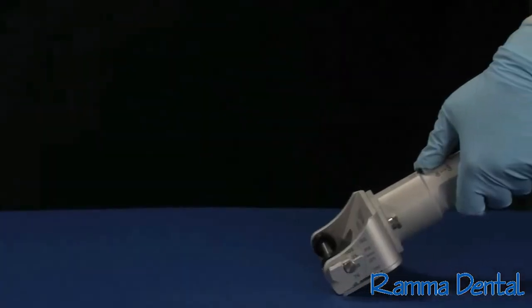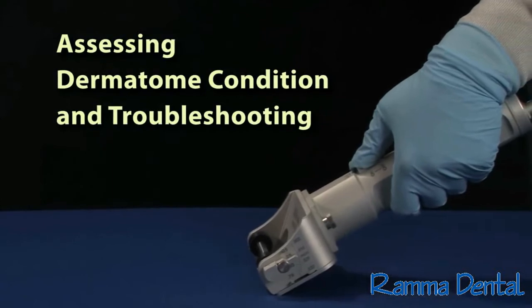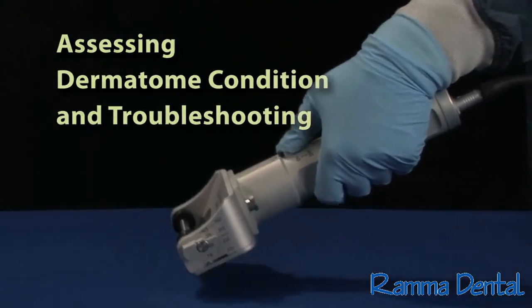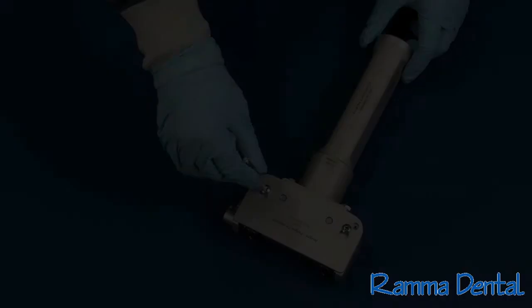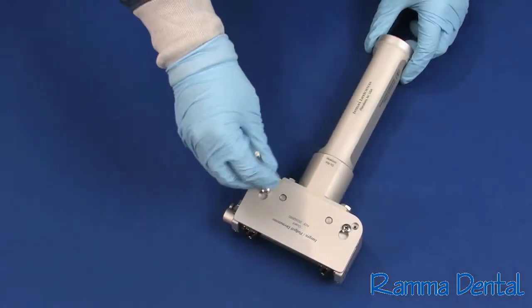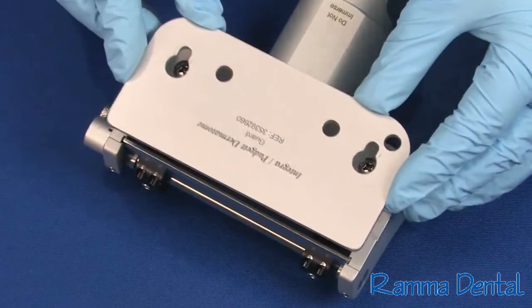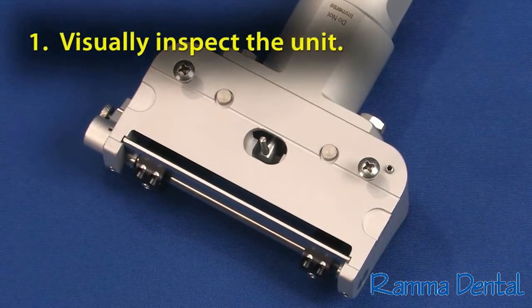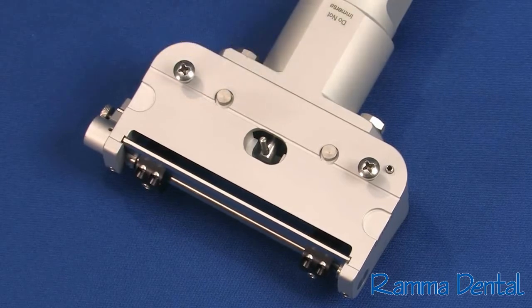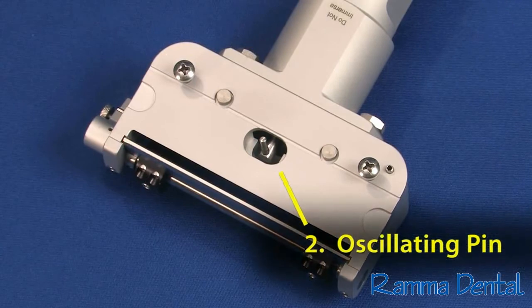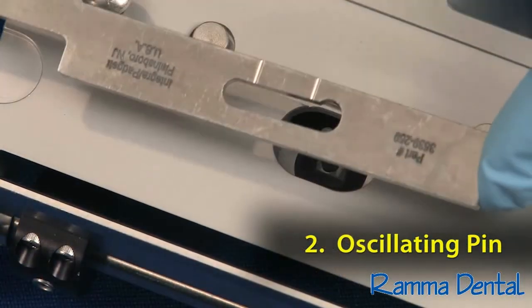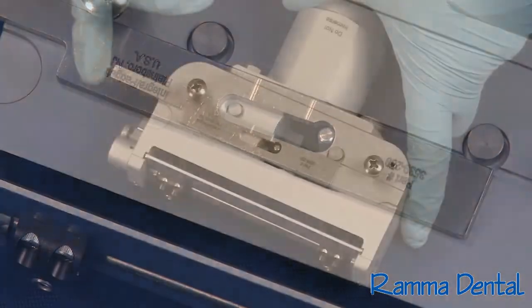The following assessment steps can be used to confirm proper dermatome operation. This assessment is to be performed without the blade and width clip installed. 1. Visually inspect all dermatome system components for signs of physical damage or wear, including loose parts, part distortion, rough edges, and areas of discoloration. 2. Check for proper oscillating pin position with the Oscillating Pin Position Guide.